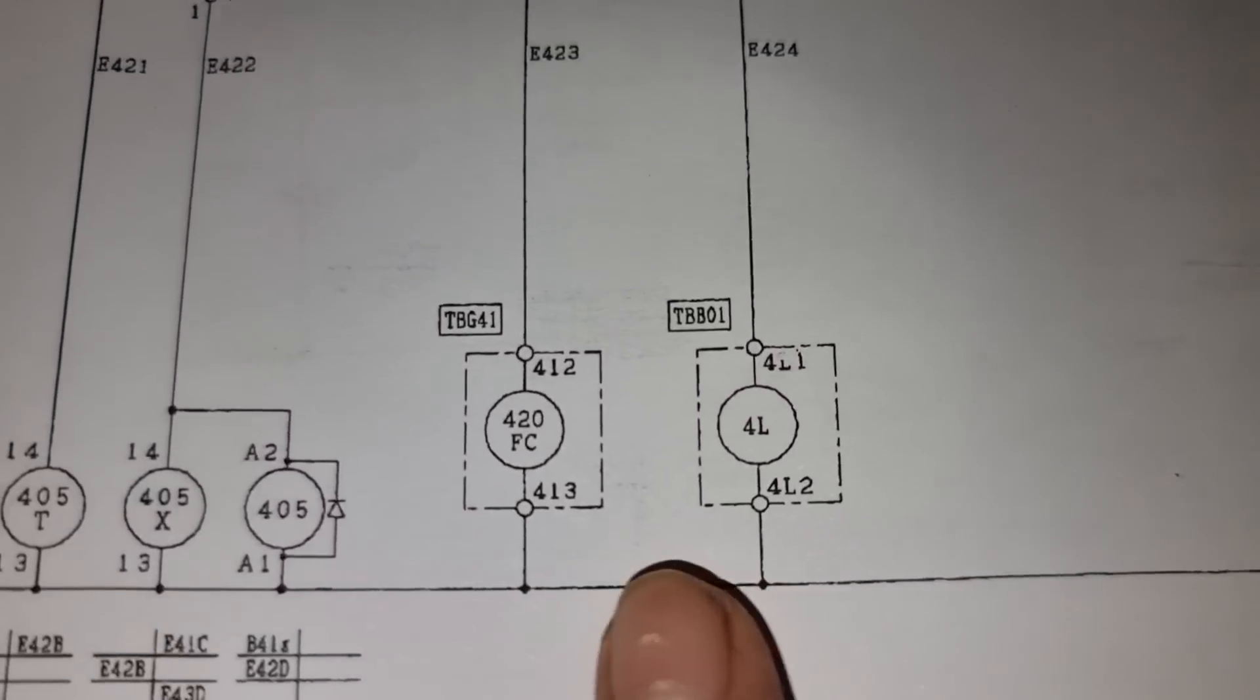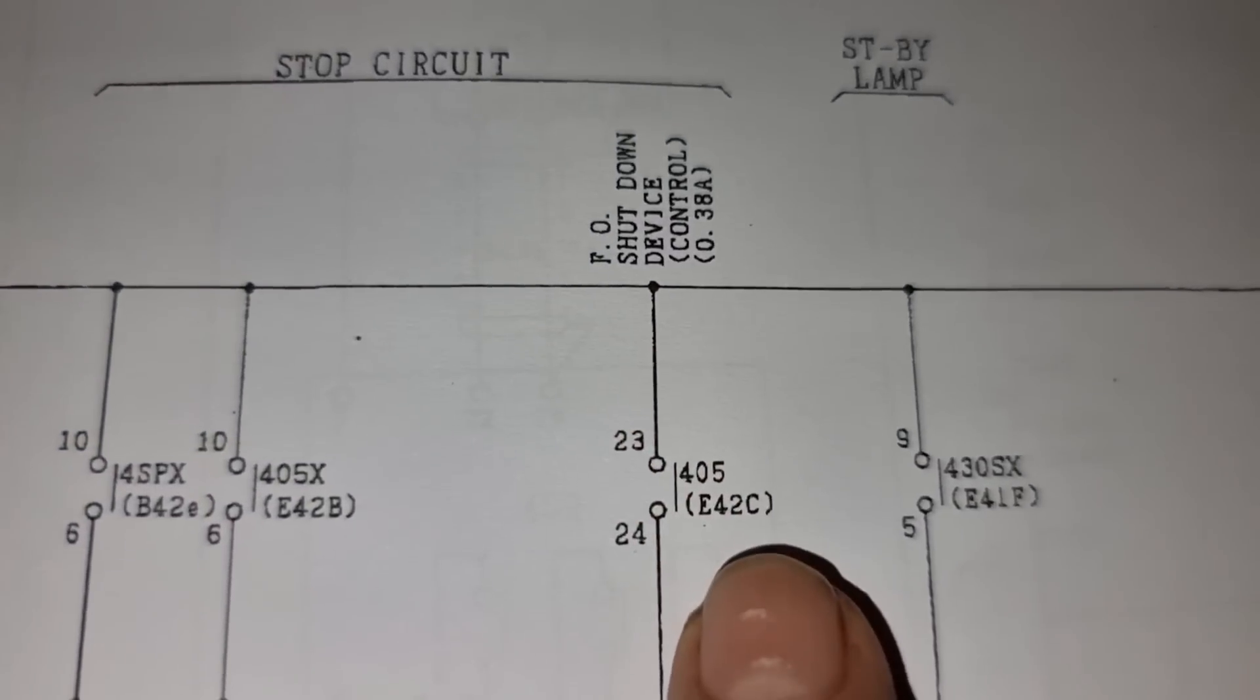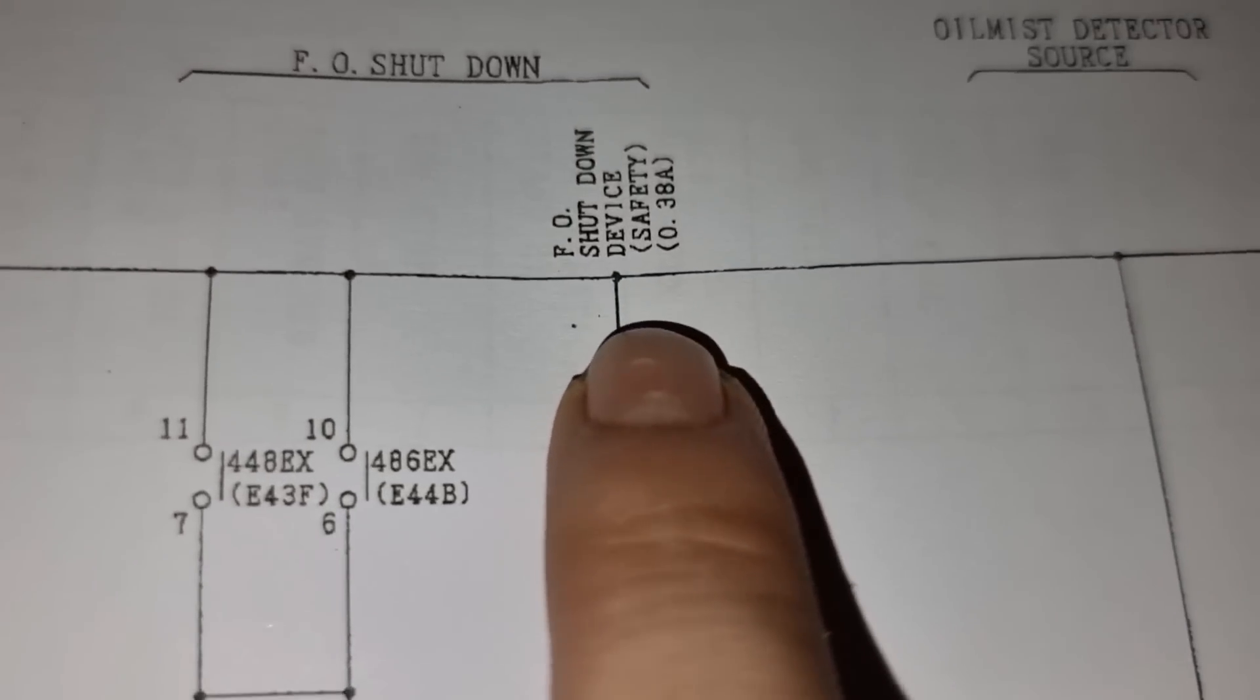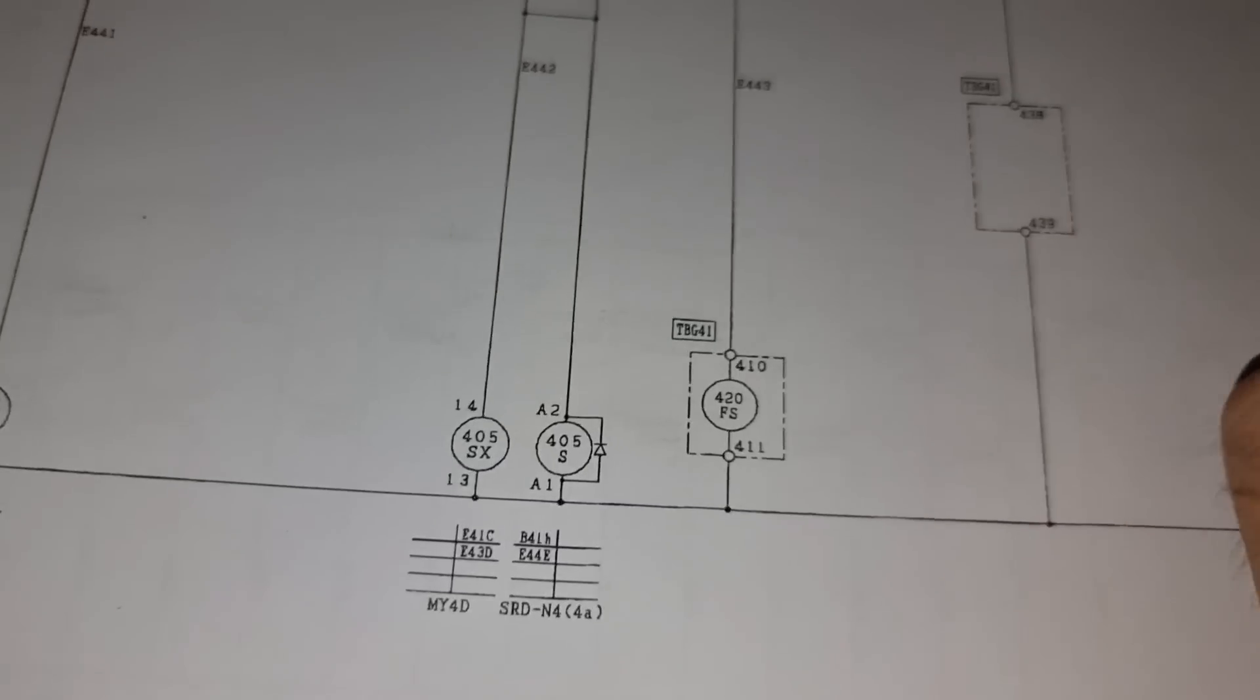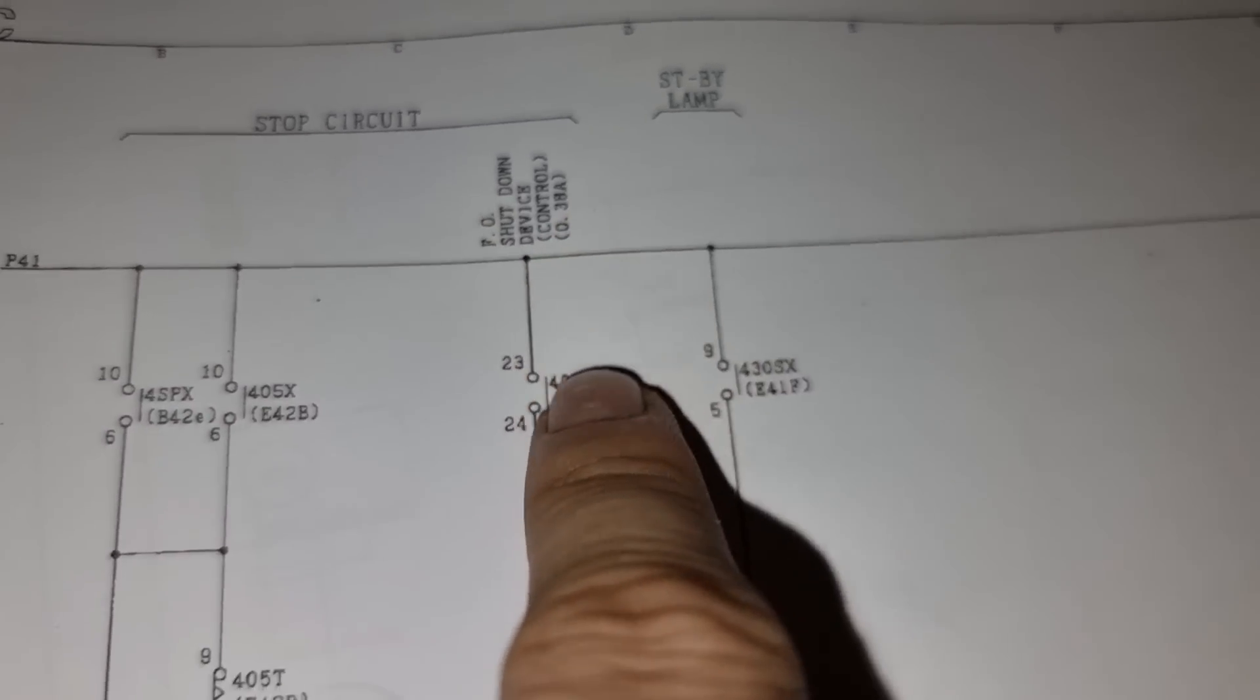And these are these two solenoid coils which I already showed it to you. So this is the control valve and this is the control valve and the other one is this safety valve 4. And we will be focusing on the stop circuit for this control valve.